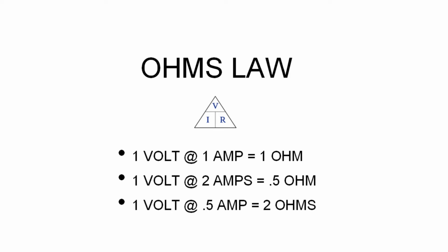This is critical later as we calculate the voltage drop between our photovoltaic panels going into the house, through copper wires usually. And we need to be able to prove to the inspector that there won't be enough resistance and voltage drop to make the system not work. The inverters, the battery chargers, and so on, just won't work if we have the voltage out there at the panels, we run through these wires, and the thing doesn't work. Well, there was too much of a drop because we didn't have the right size copper wires. So that, in essence, is what Ohm's law is about.